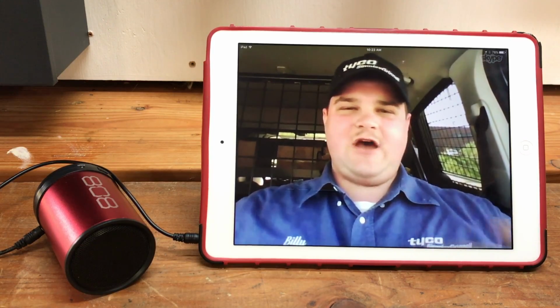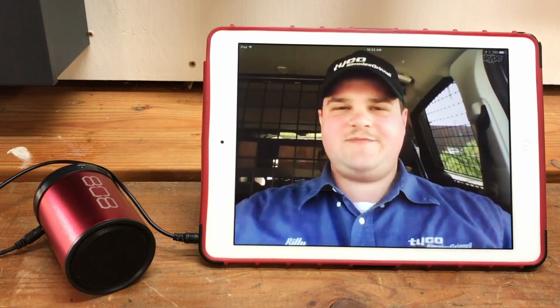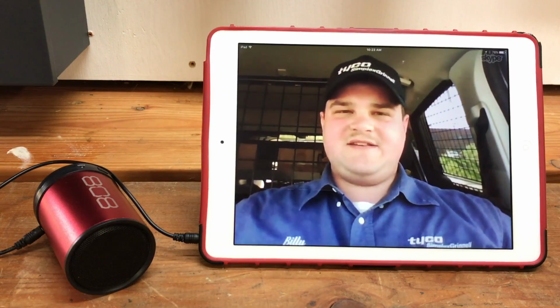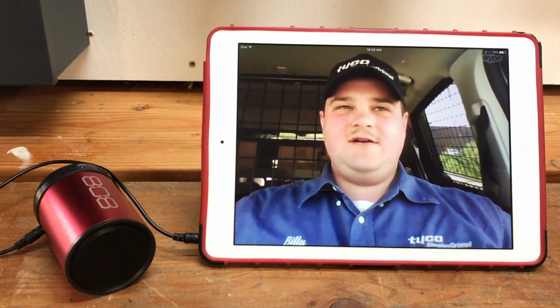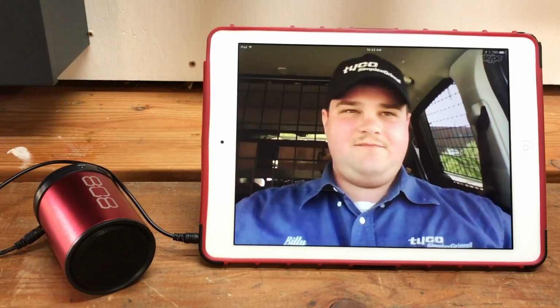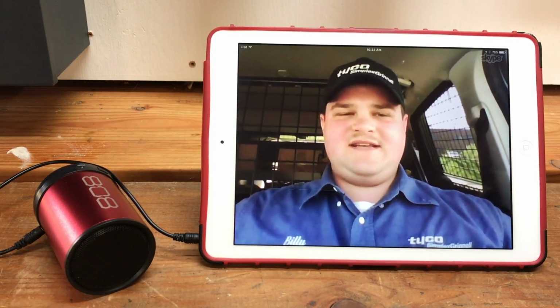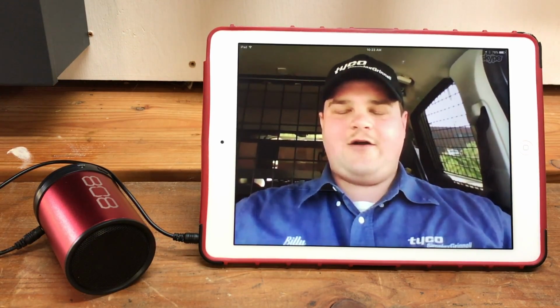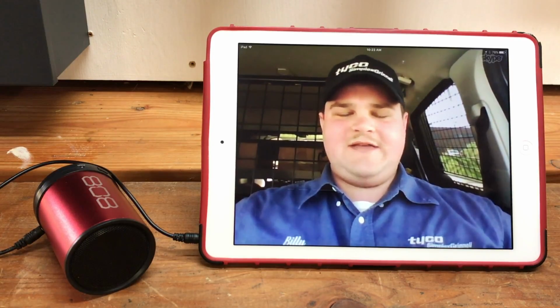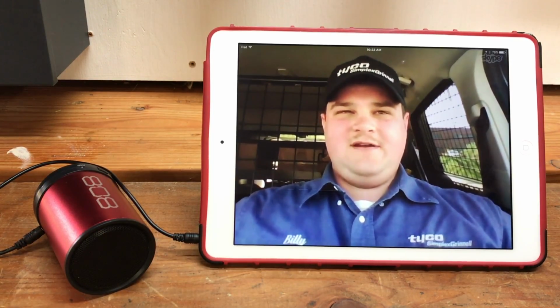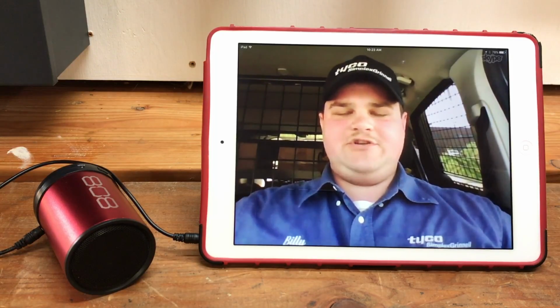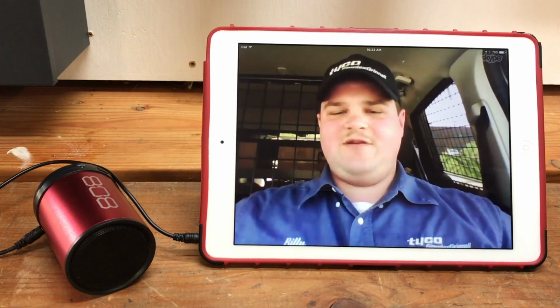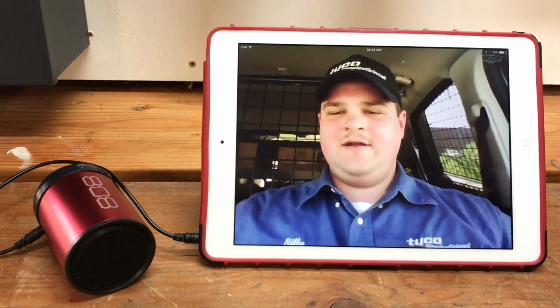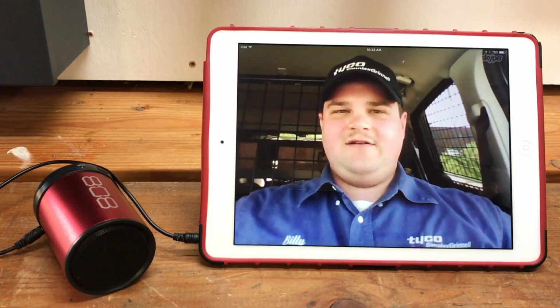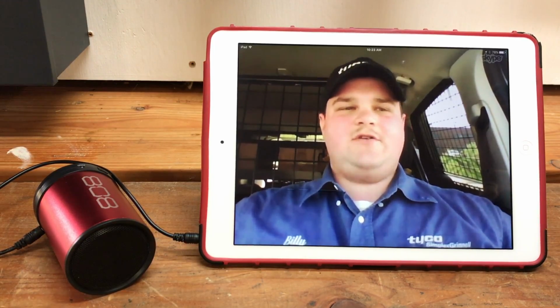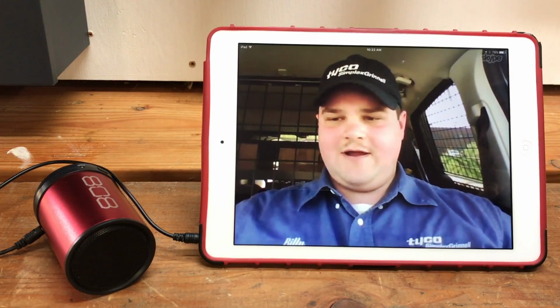Now they basically operate as speakers, our True Alert speakers. You'll mostly find these in hospitals and places where you have patients or critical events going on inside a facility, where you don't want an actual fire alarm to startle whoever's inside. You want more of a mellow type notification, to where it'll just notify certain staff members that there's an issue going on that needs to be addressed, without constant, shrill, loud noise being generated throughout the whole facility.